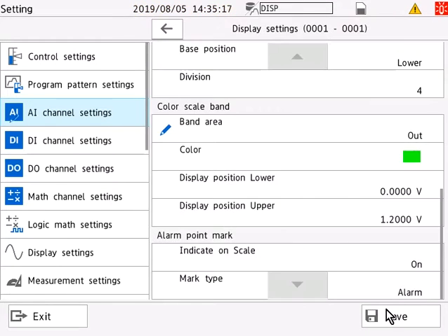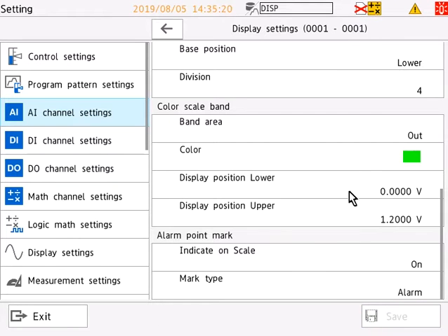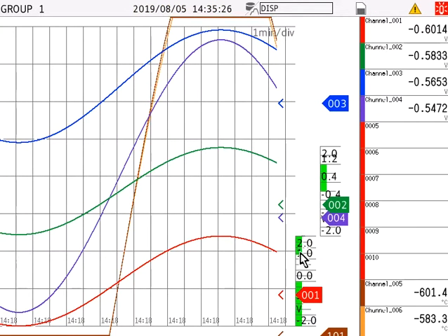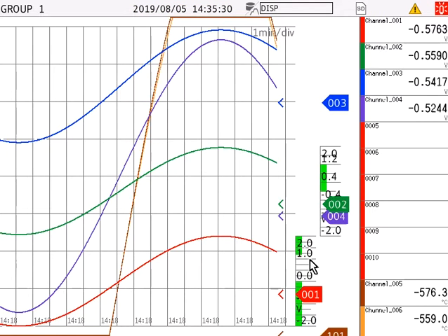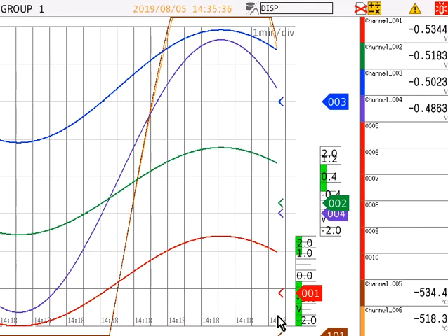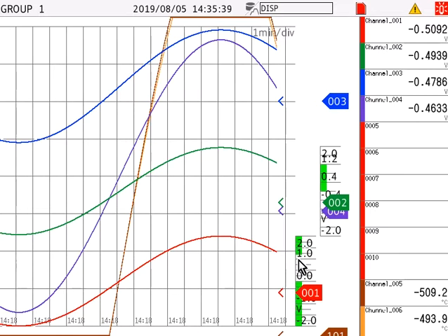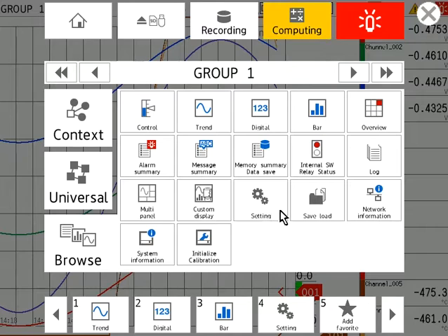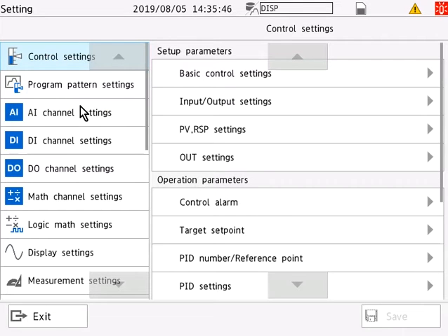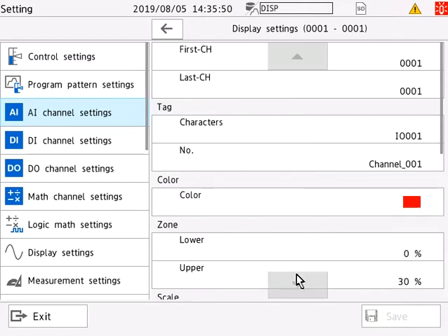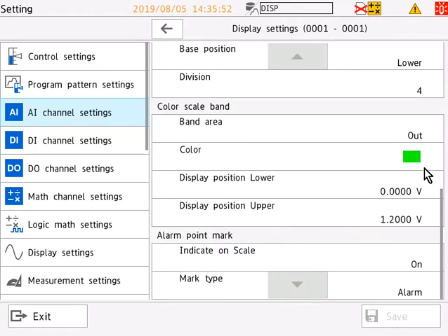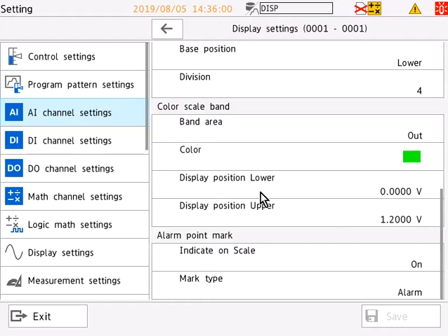Whereas if we select out, this will highlight every part of the range besides this selected range. So if you notice, on a certain scale, since we're only dealing with channel 1, only channel 1 scale is affected. Whereas if we deal with channel 2, then we would also change this channel, but right now we're only dealing with this. So if you notice, since we set it to out, the parts of the range not highlighted are selected. This would potentially help an operator to quickly tell if certain parameters are being breached using a visual indicator. And that's why we designate these ranges with the display position lower and display position upper values, which you can enter manually.